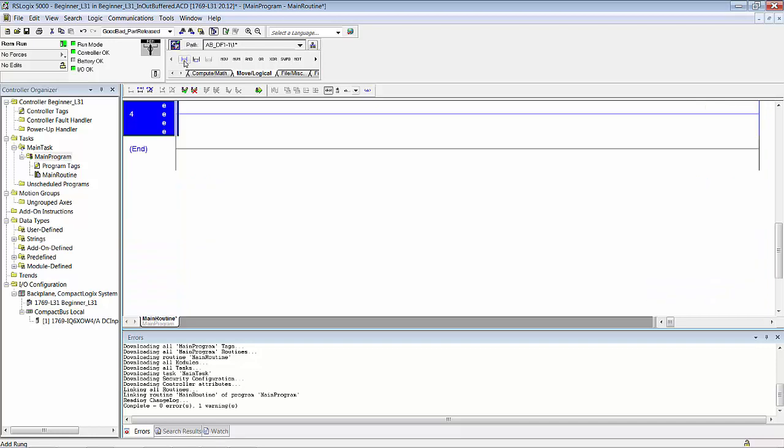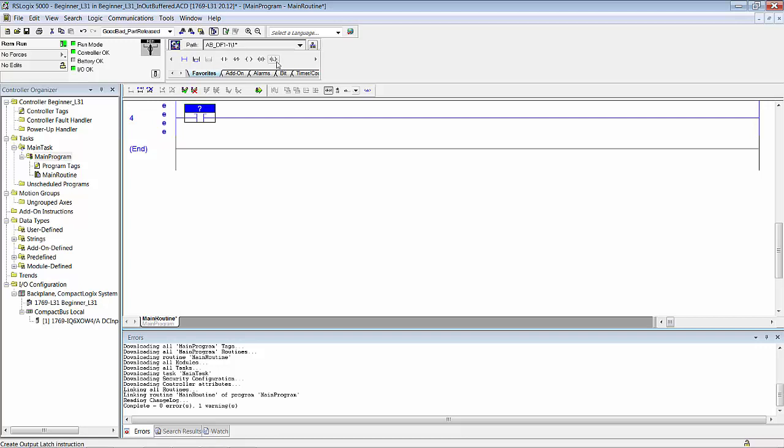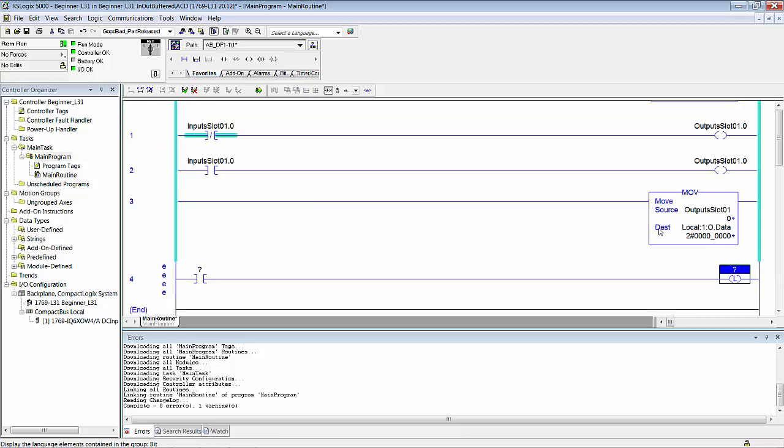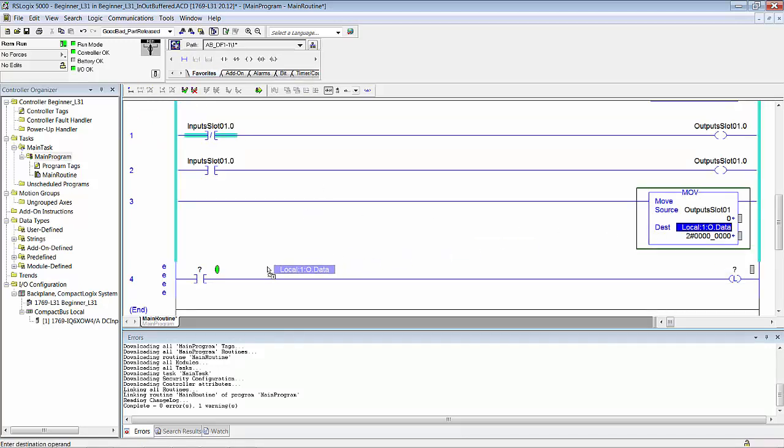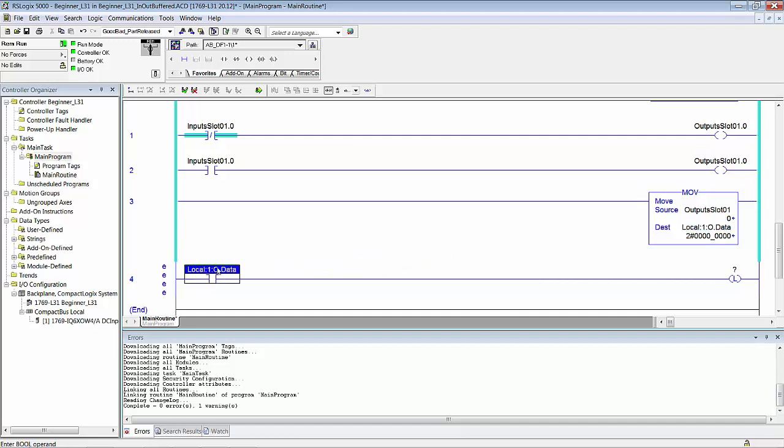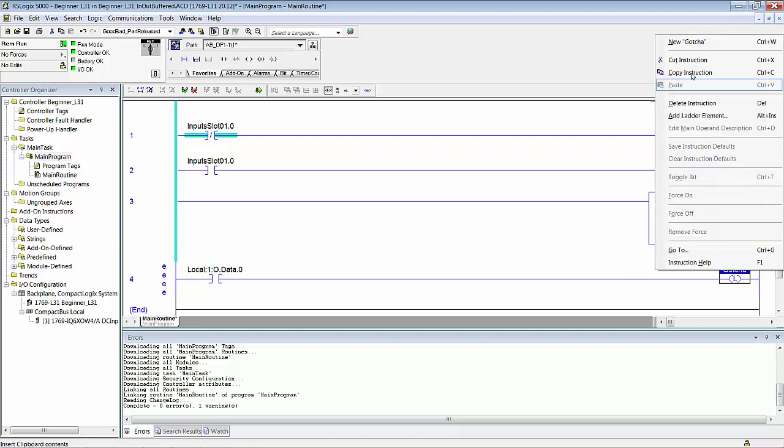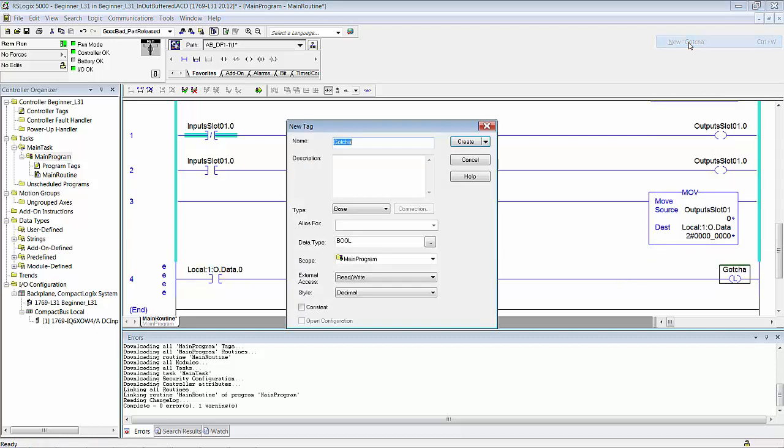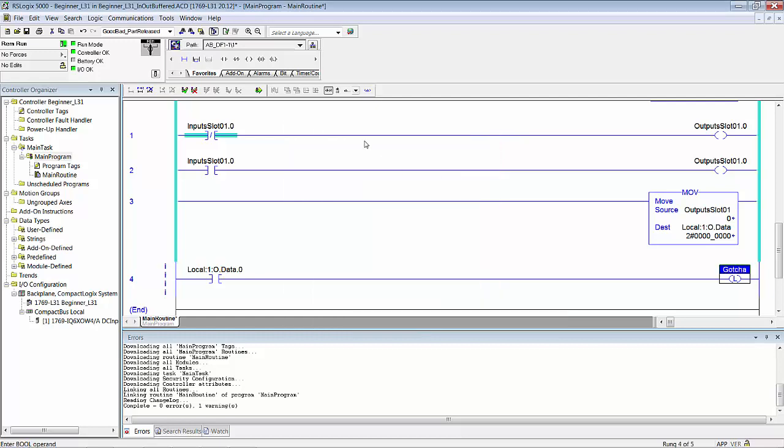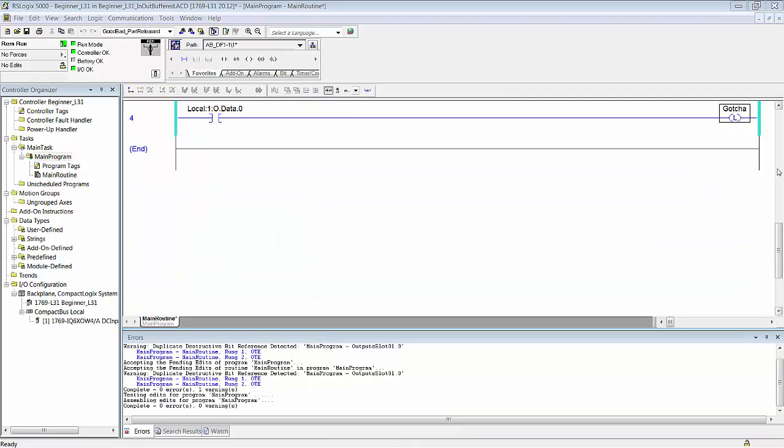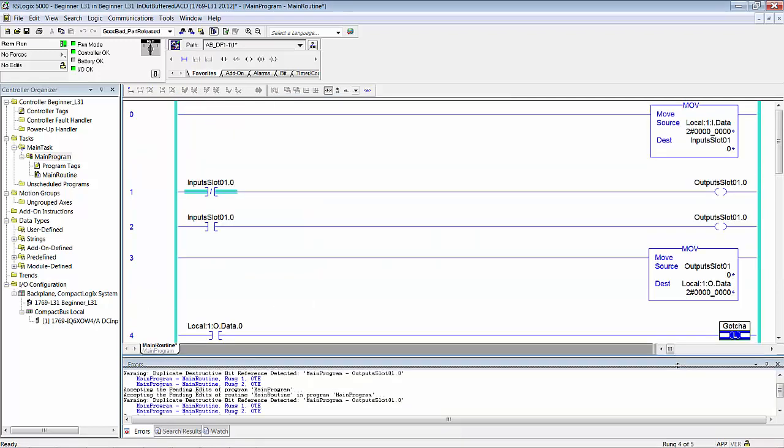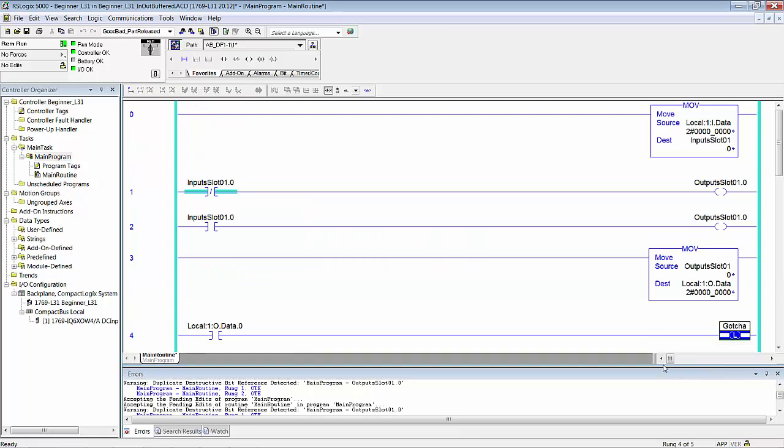Well, we're going to jump ahead here. This is free, this wasn't in the manual. It's something that I find interesting. So I'm going to take this tag, drag it down here. Edit the tag to be just bit zero—you can't read a word with that type of instruction. We'll call this gotcha. Okay, that's a new tag name: gotcha, Boolean, main program. Finalize all edits. Now we'll drag that down and wait till we see this turn highlight to show that that bit—see, that bit went on. It just went on.